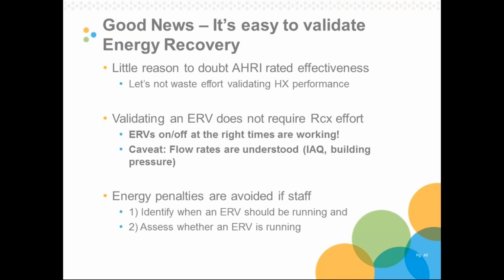And validating energy recovery doesn't require a recommissioning effort. ERVs that are on or off at the right times are working. That's it. Okay, there's one important caveat, and that's that we know the flows through that unit, but that's not really an energy recovery problem. That's a ventilation problem, where we're meeting ventilation loads for indoor air quality concerns, maybe some building pressure requirements. Again, ERVs are operating on those ventilation flows, so as long as we have those characterized and our ERVs are on and off at the right time, they're probably doing their job. So the bottom line is energy penalties can be avoided by validating ERVs if staff can identify when an ERV should be running and then assess whether an ERV is running.